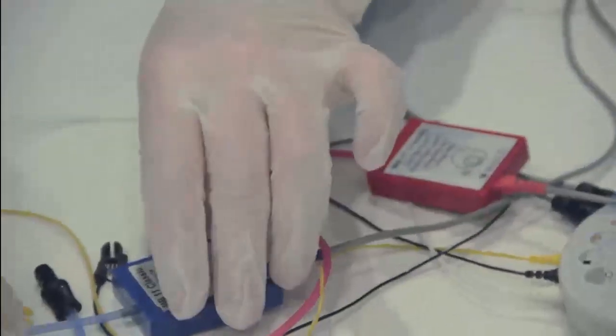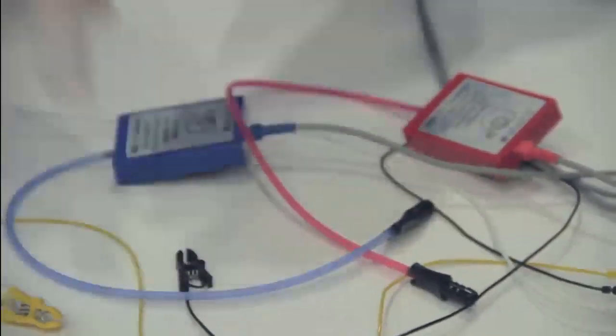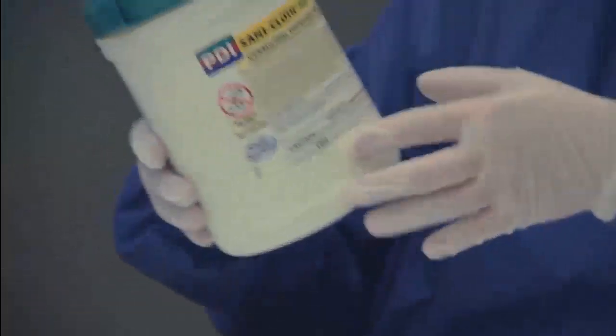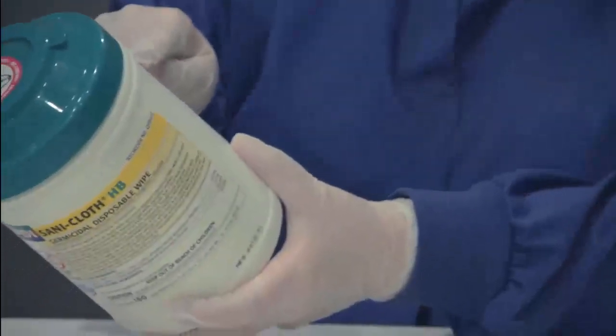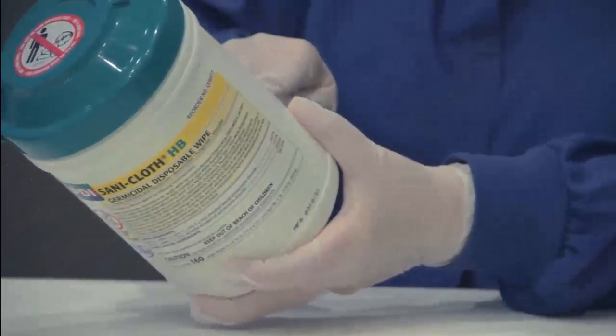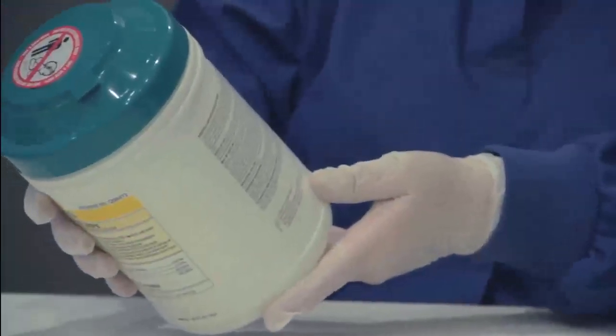Non-disposable components of the hardware that touch the baby or the baby's bedding should be wiped with a disinfectant wipe after use on each baby. Use of a non-alcohol-based disinfectant product is recommended. If alcohol-based disinfectant is used, the earphone tubing material may be affected over time, causing it to harden and crack. The tubes will need to be replaced on a more frequent basis. Be sure to follow the directions for use and handling precautions on the disinfectant product. Allow the disinfectant to dry thoroughly according to the manufacturer's recommendations before using the Classic on the next baby.